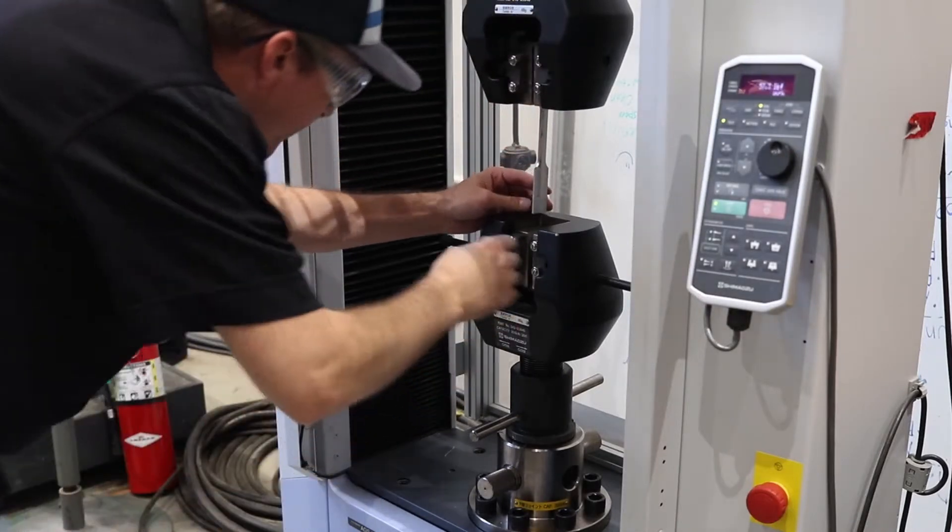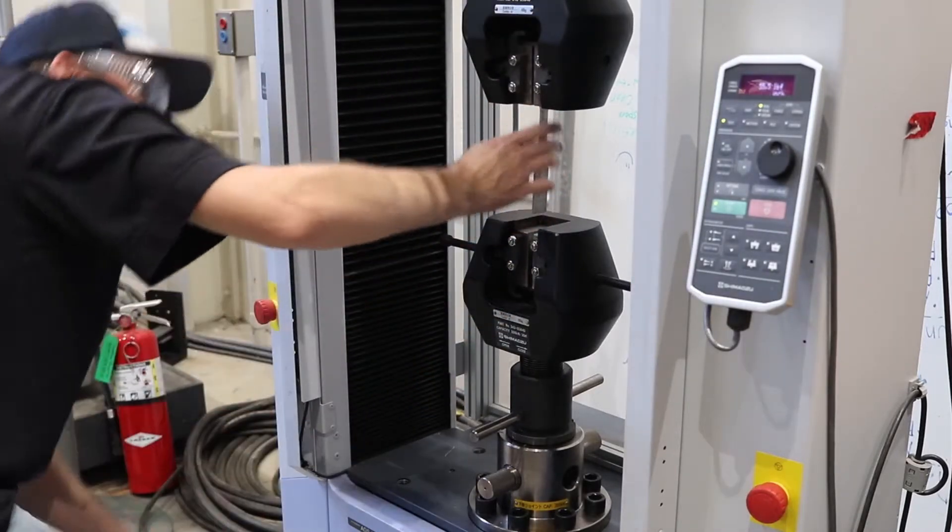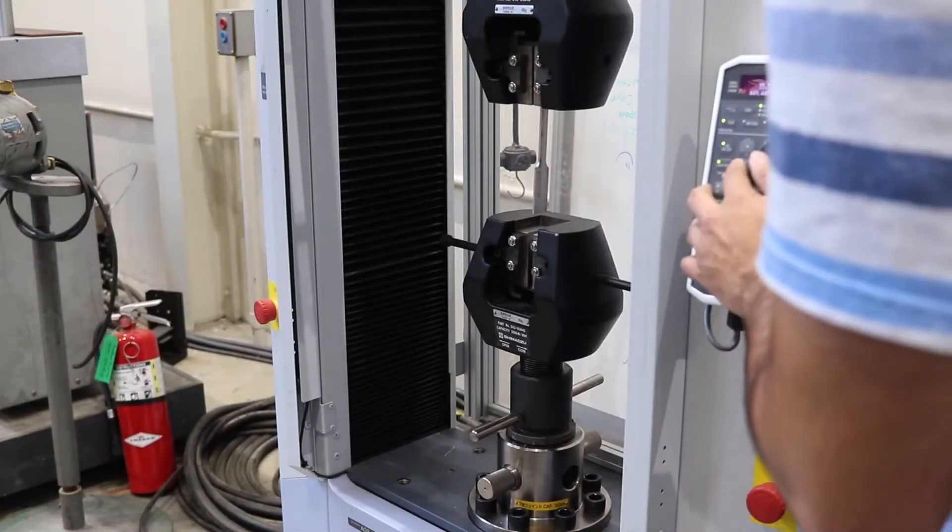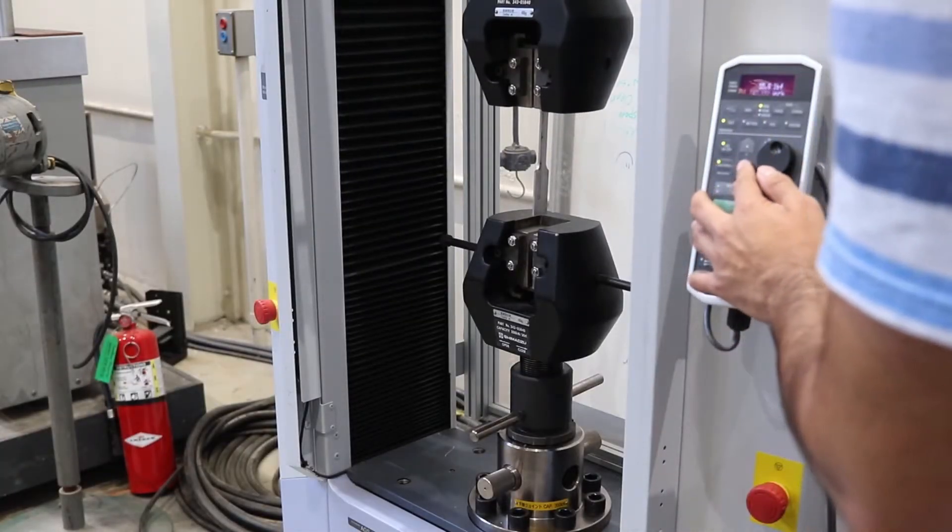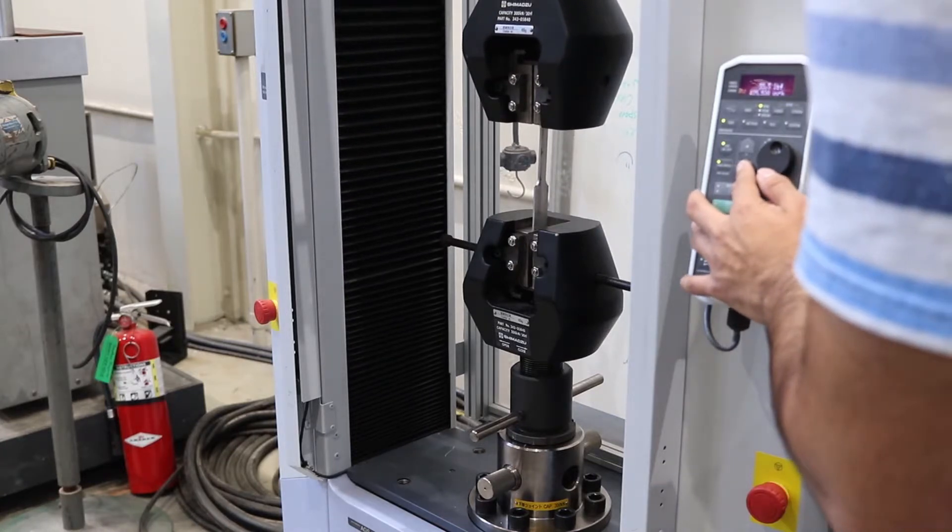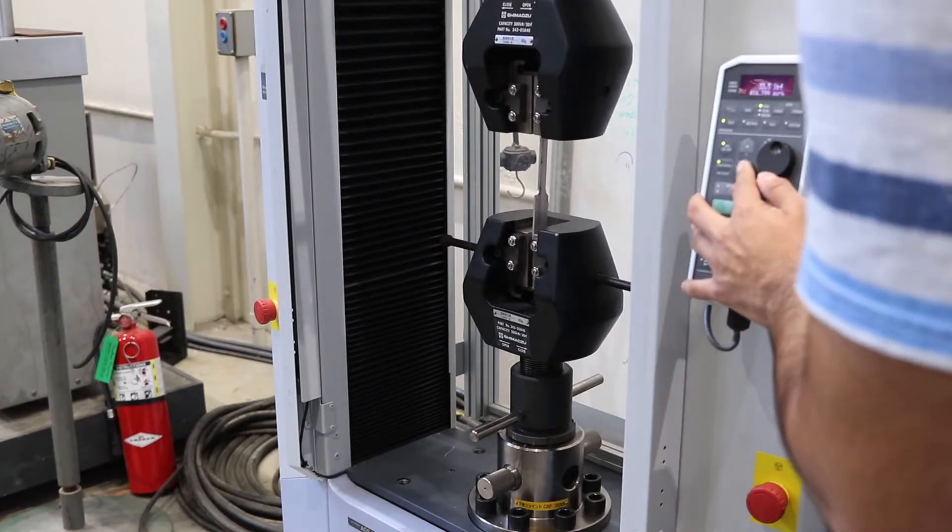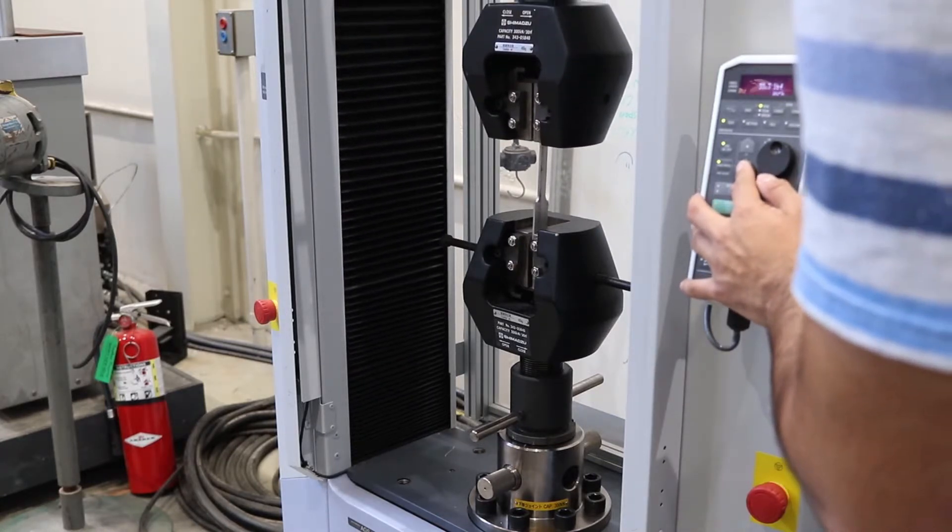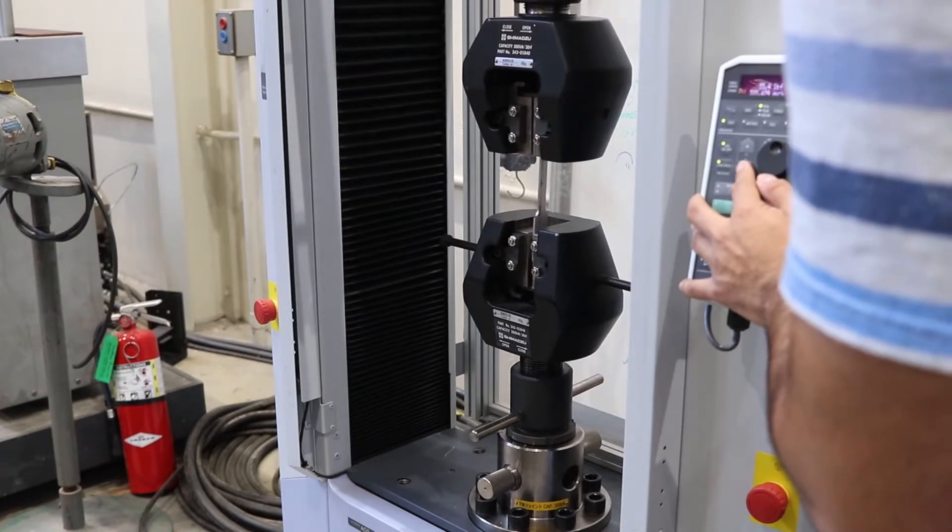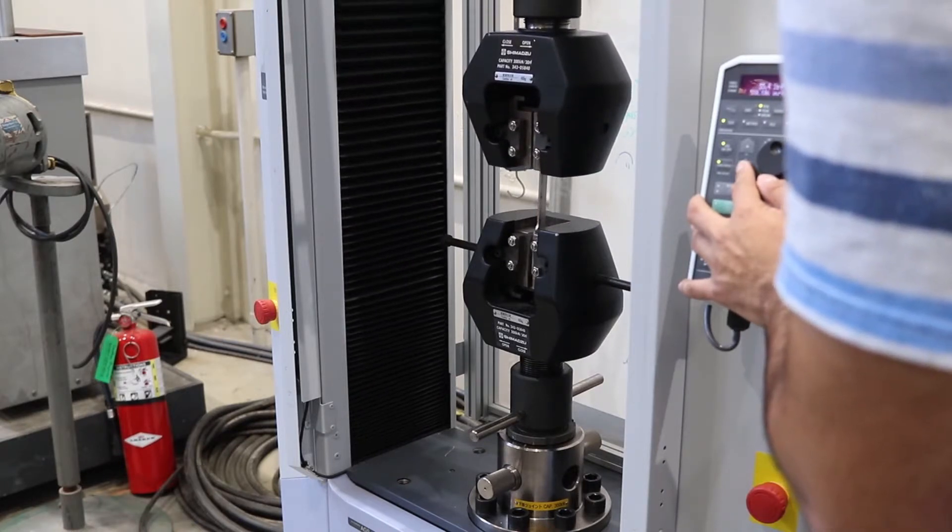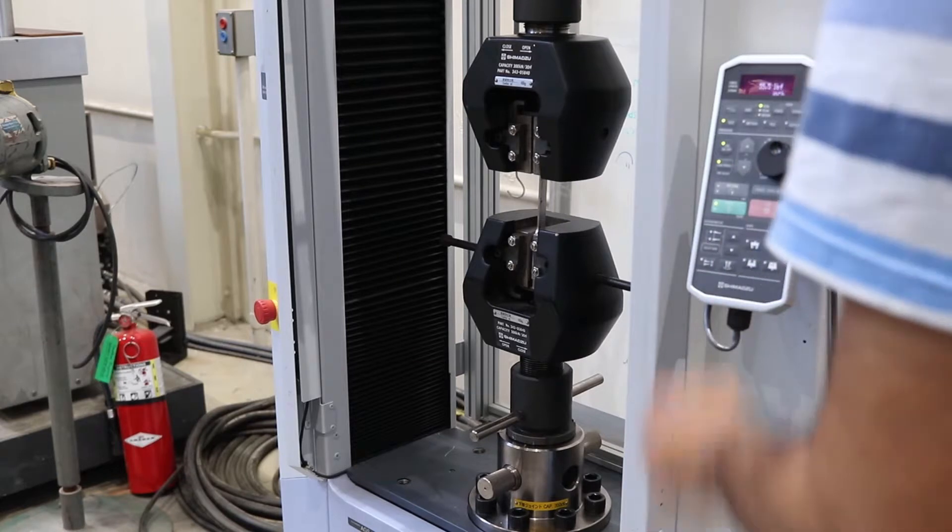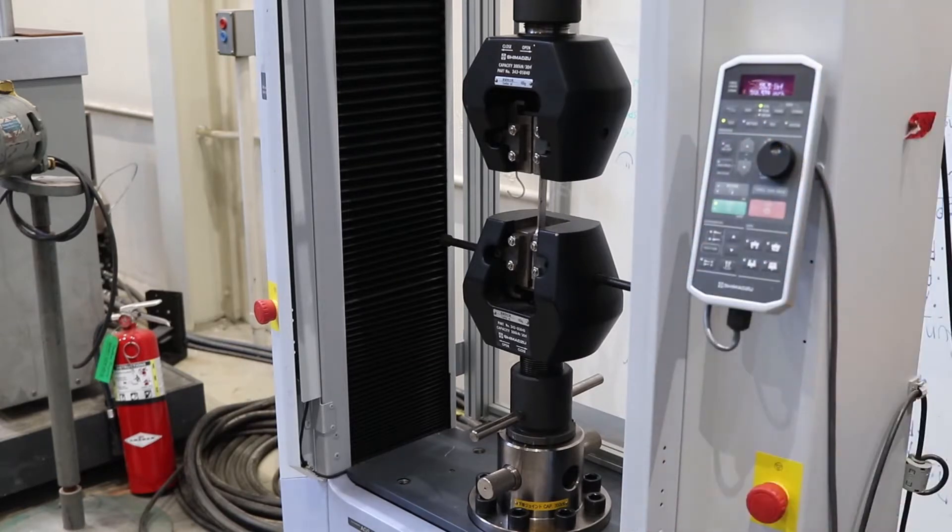Now that the upper jaw is secure, we need to jog the machine down so we can secure the lower jaw. To do so, we click jog on off, high speed, and press the down button. Again, the specimen should align with a scribe in the face of the jaw. After we are done jogging the head, we press the jog on and off and high speed off.